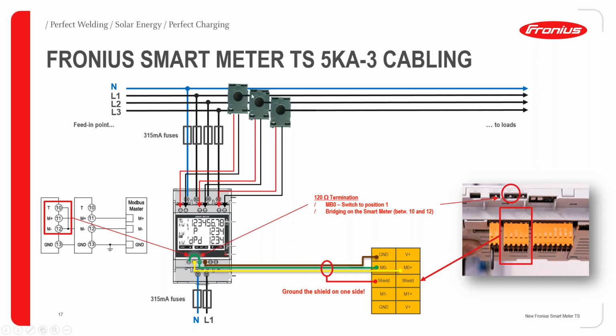But then if you look into the phase cables, you are not going to put the cables directly into the smart meter. You are going to use current transformers for the current measurements here. And another very important thing, if you see the bottom of the smart meter, you can see neutral and phase 1 connection. This means you need to provide external power supply for this smart meter. So that's very important.